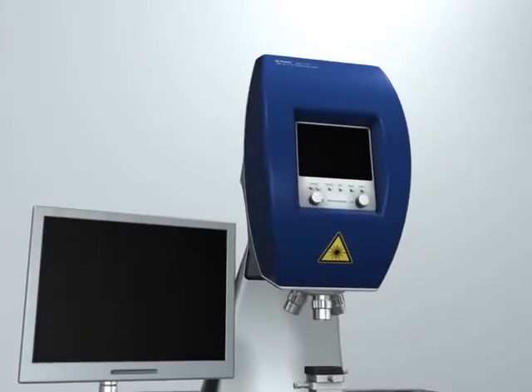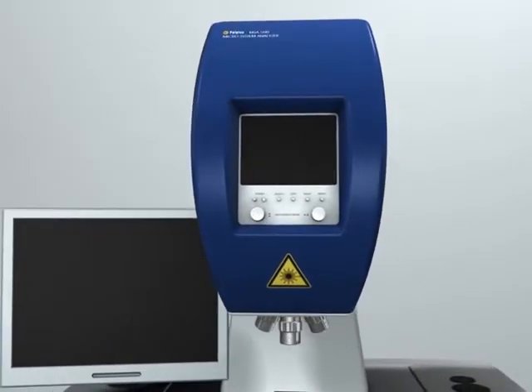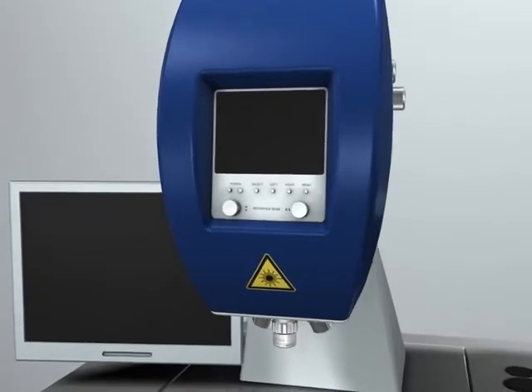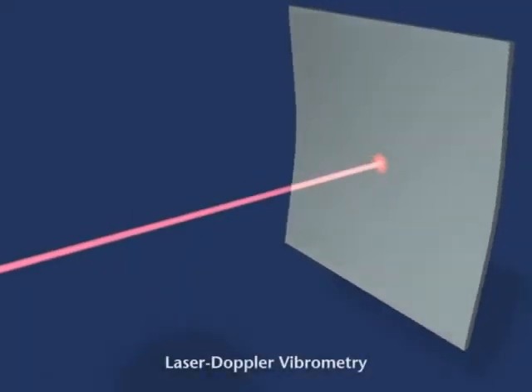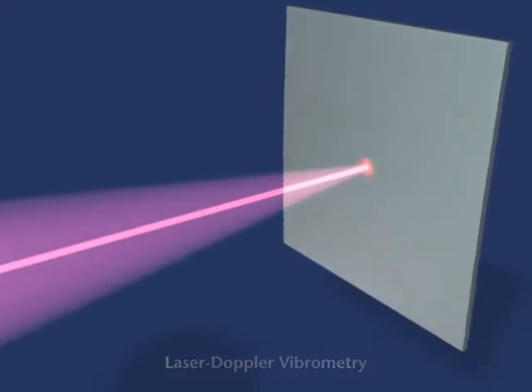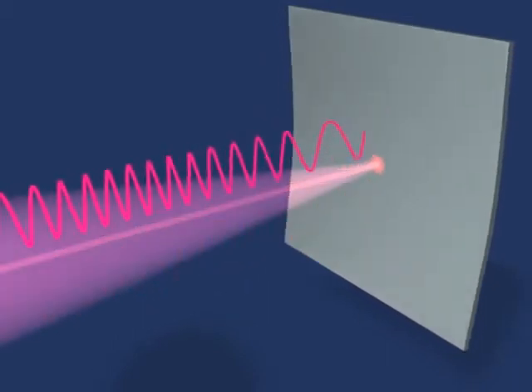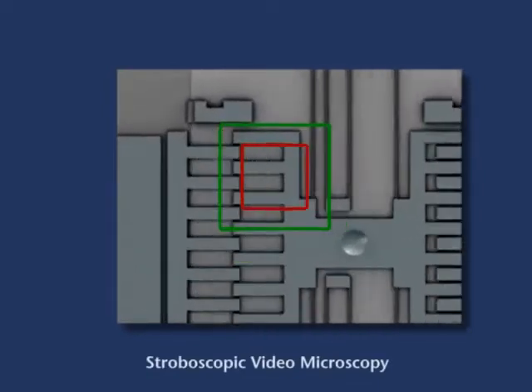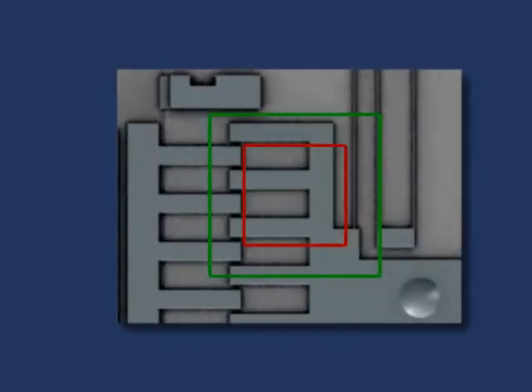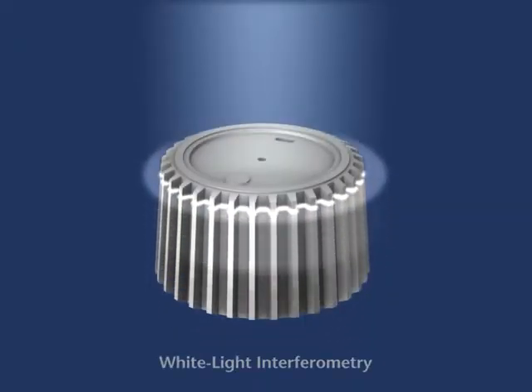Polytec's Microsystem Analyzer characterizes MEMS devices by combining three light-based sensor technologies into one versatile measurement microscope: scanning laser Doppler vibrometry for fast sub-nanometer measurement of out-of-plane dynamics up to 24 MHz; stroboscopic video microscopy for measurement of in-plane motion with nanometer accuracy; and scanning white light interferometry for high-resolution static topography measurement.